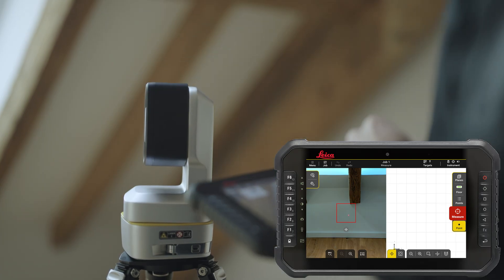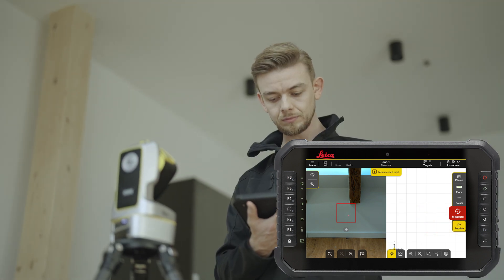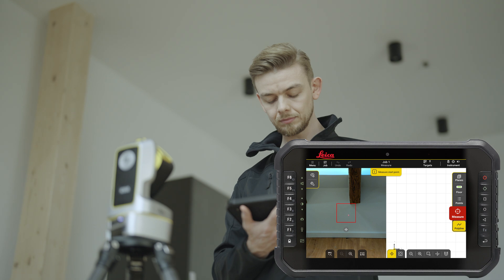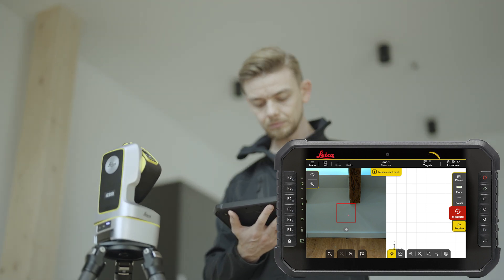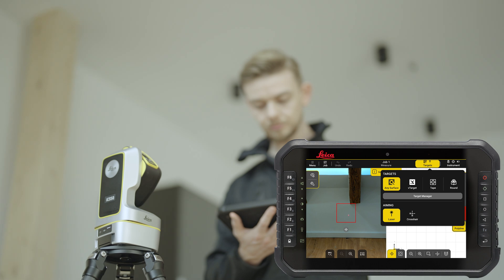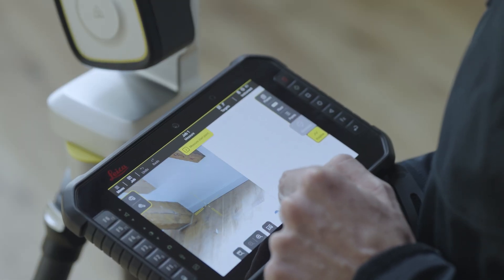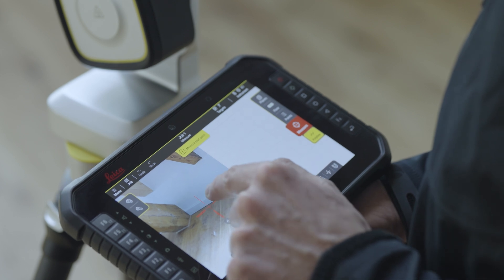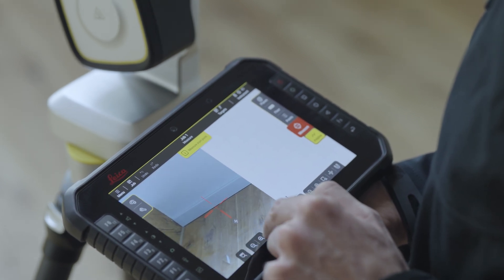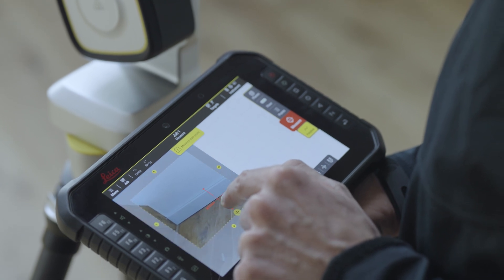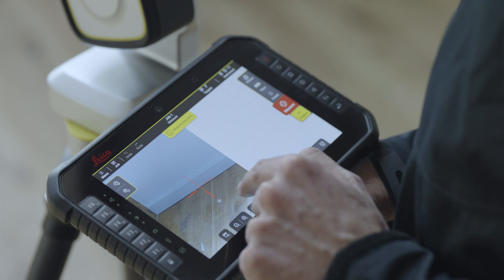Select one of the measuring features such as point, line, or polyline. When the laser pointer is set as active, a rough aiming area is displayed. Tap the Targets button on the top bar and switch between laser and crosshair. Turn the instrument by hand or single tap on the image to aim roughly to a certain location. Use Minus and Plus or the Max Min button to quickly zoom in and out. When the crosshair stops blinking, the instrument is ready to measure.